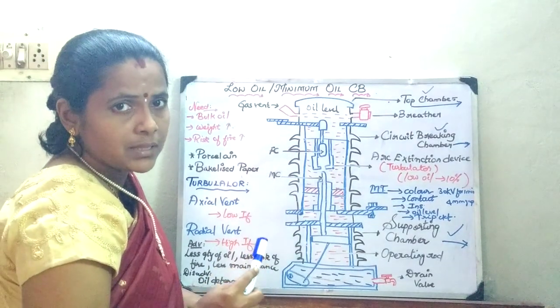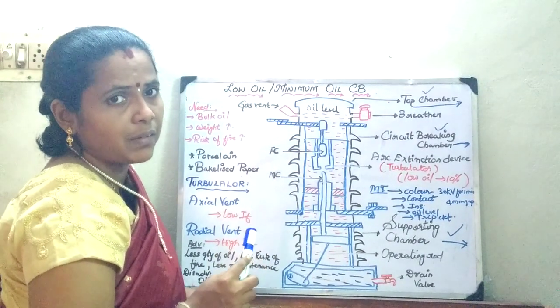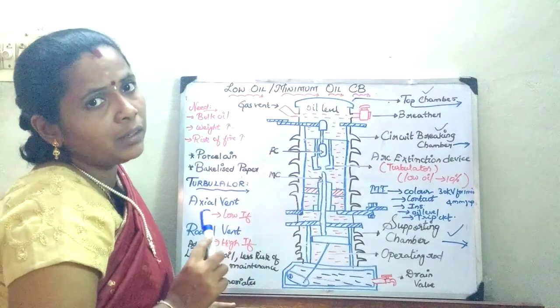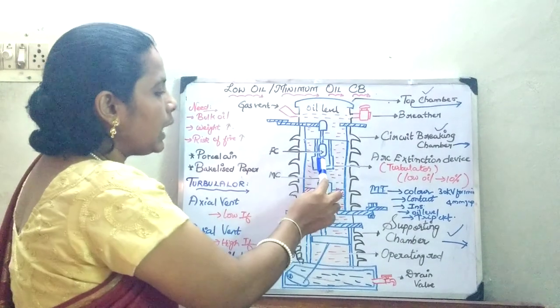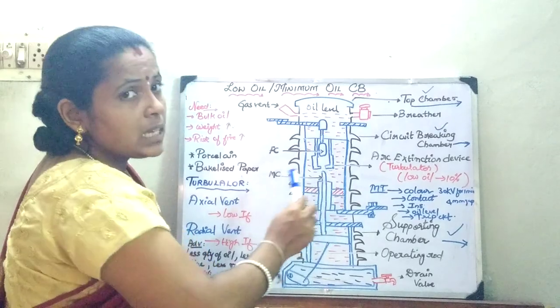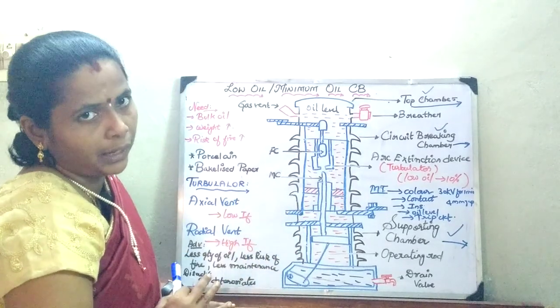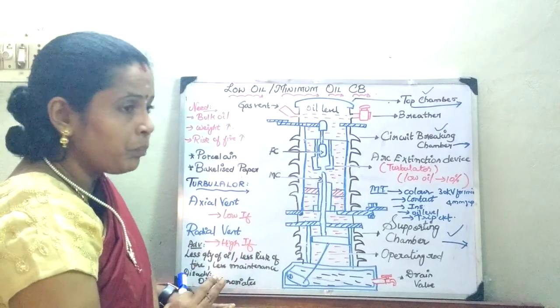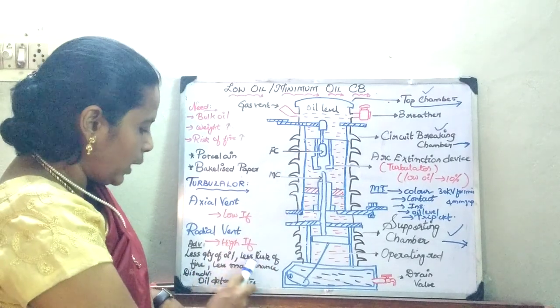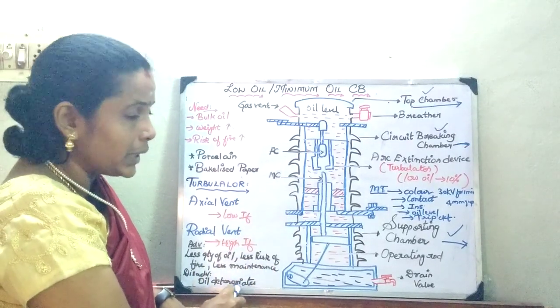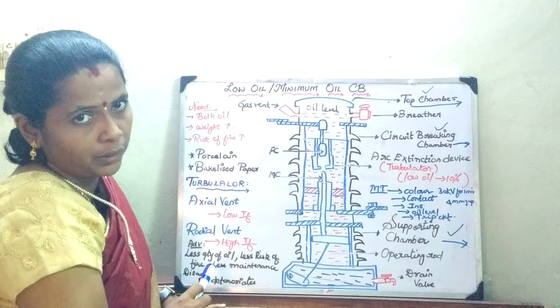Thereby the degree of carbonization or contamination gets reduced in your supporting chamber. Since the arcing products remain in the oil, certain maintenance is required though it is risk free. The main problem is due to high degree of carbonization, the oil gets deteriorated.